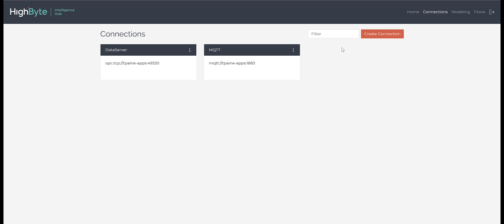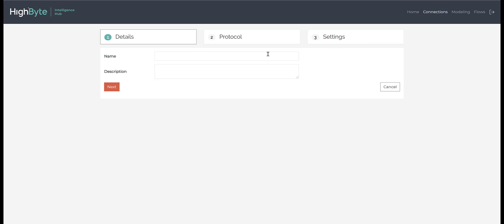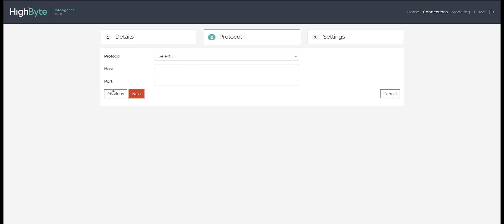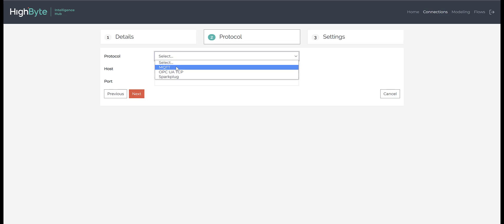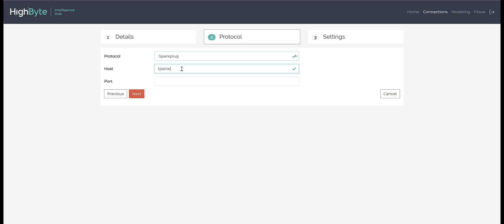We begin the process of configuring Sparkplug within the HighByte Intelligence Hub by creating a Sparkplug connection. This is done by creating a new connection and assigning it a unique name. We'll then select the Sparkplug protocol and enter the host and port of the MQTT broker that our Sparkplug clients will subscribe and publish to.